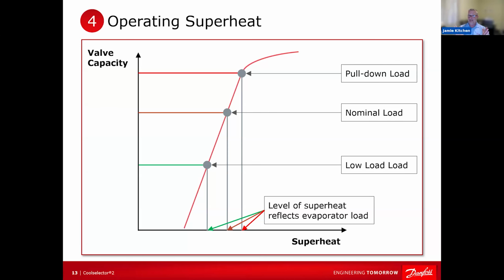If you ever run into an unstable system like that and you've checked your subcooling, you have enough refrigerant charge, increase your superheat slightly until it stabilizes. Love that. Increase another 0.5 degree, and you're golden, man.